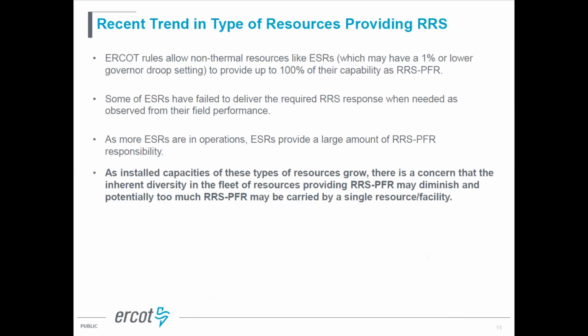So putting those things together, for inverter-based technology, ERCOT rules allow them to set their governor droop as one percent. That means they can provide up to 100% of their capacity as RRS-PFR, and some of them may have failed to deliver the response. We've also seen ESRs already providing a large share of the RRS-PFR. So our question is: is there any concern if RRS-PFR in the future becomes concentrated on a few large resources? That is a concern.